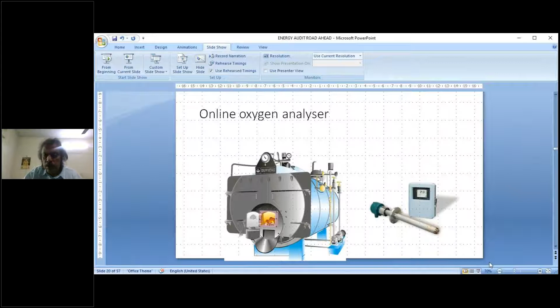How does he know whether it is too much air or too little air? So he needs some kind of an input. That input comes from this oxygen analyzer. If you put it in this chimney, this will indicate the oxygen in the exhaust. The oxygen in the exhaust is an indirect indicator of the air you are using for combustion. So these are also important in an energy efficiency exercise. Instrumentation can reveal a lot of things which are otherwise hidden.